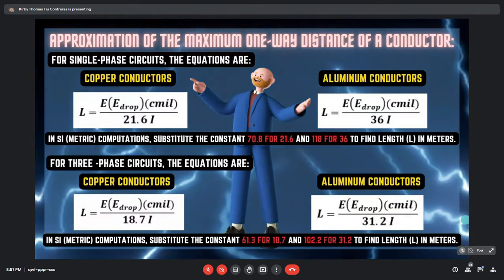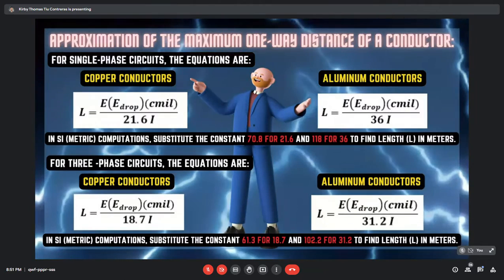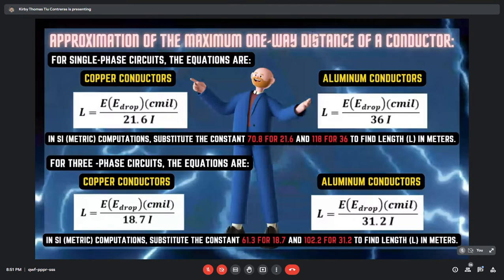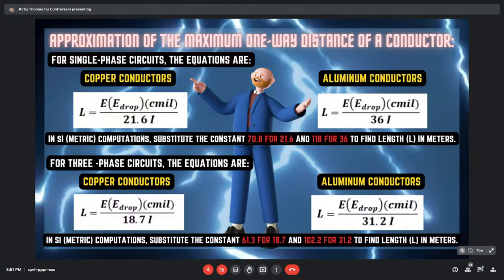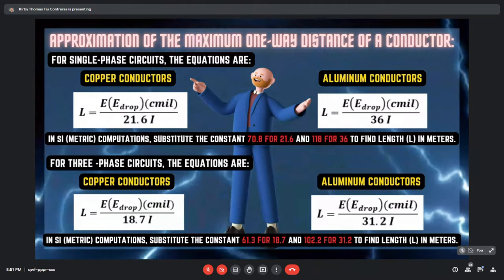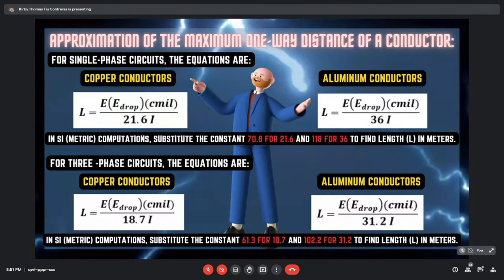Next, approximation of the maximum one-way distance of a conductor. For single-phase circuits, this is the equation. For copper conductors, L is equal to E times voltage drop times circular mil divided by 21.6 I, and for aluminum conductors, L is equal to E times voltage drop times circular mils divided by 36 I. In metric computation, substitute the constant 70.8 for the 21.6 for copper conductors, and for aluminum conductors, 118 for the 36.